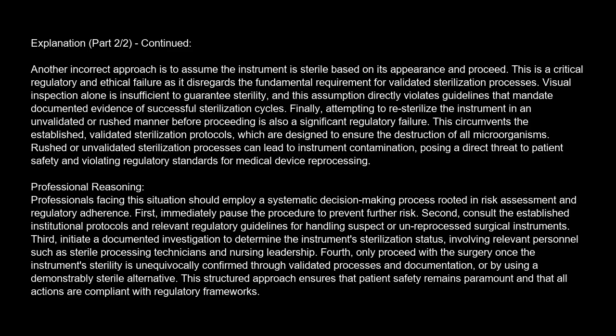Finally, attempting to re-sterilize the instrument in an unvalidated or rushed manner before proceeding is also a significant regulatory failure. This circumvents the established, validated sterilization protocols, which are designed to ensure the destruction of all microorganisms. Rushed or unvalidated sterilization processes can lead to instrument contamination, posing a direct threat to patient safety and violating regulatory standards for medical device reprocessing.